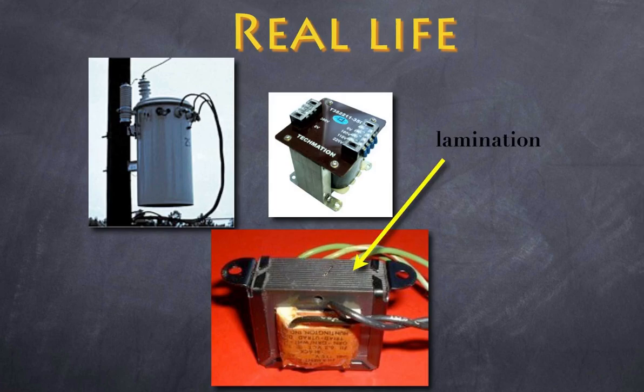To reduce eddy currents, instead of using a solid iron core, the core is laminated — made up of thin metal sheets separated by a thin layer of insulation. This disrupts the eddy currents, so while there may be small eddy currents within each sheet, they are significantly reduced. However, because some eddy currents still form, large-scale transformers need cooling systems to absorb the heat generated.